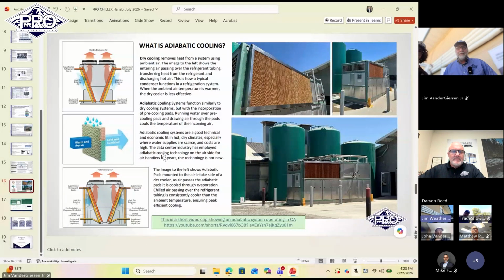What this slide shows is the adiabatic pads mounted on this chiller system to the right. The diagram to the left is showing a standard system, a dry cooler without adiabatic, and how typically the outside air will enter that condenser, and then exit through the top. We throw the adiabatic pad in that airstream, pre-cooling the air before it goes into the condenser or the gas cooler.